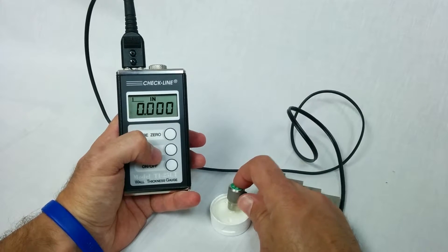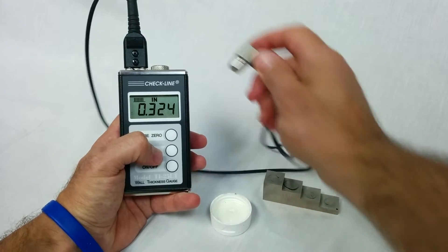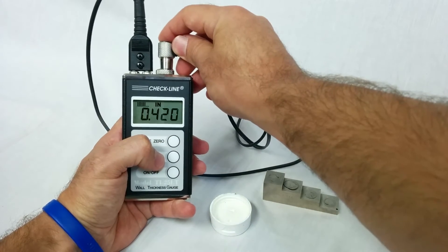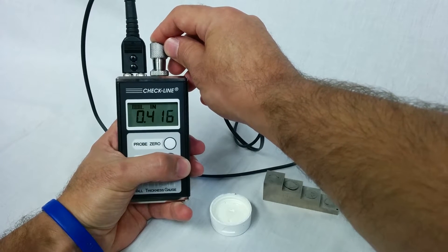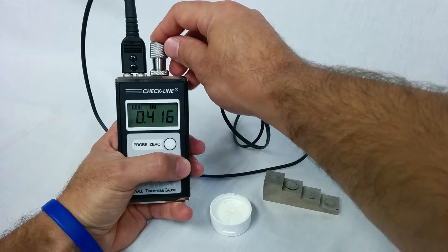Next I'm going to put some coupling gel on the transducer and press it against the battery cap. Then I'm going to press the Probe Zero key and it's going to reset the probe just like zeroing out a micrometer.